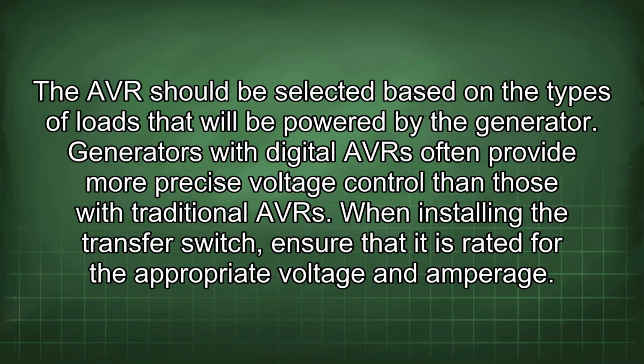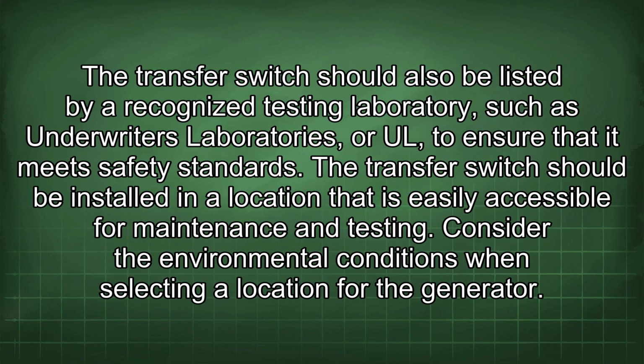When installing the transfer switch, ensure that it is rated for the appropriate voltage and amperage. The transfer switch should also be listed by a recognized testing laboratory, such as Underwriters Laboratories, or UL, to ensure that it meets safety standards. The transfer switch should be installed in a location that is easily accessible for maintenance and testing.